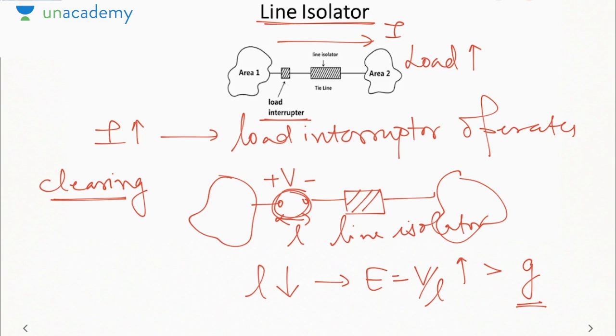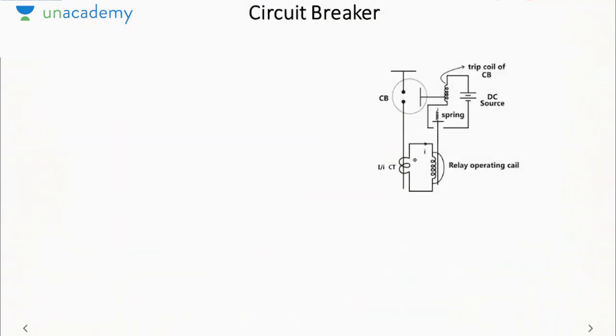So what it means is, there are 3 types of switches which operate under specific conditions. But I want to have a more general type of switch which can operate under any condition at my command. Because here I am not controlling any type of switch. One is operating under abnormal condition by itself, one is operating at full load condition by itself, other is operating at no load condition. But I want control. That is, I must be able to operate the switch whether abnormal conditions are there, or full load or no load. I must be able to control it. Such a switch is called your circuit breaker. So a circuit breaker is a switch which can operate under abnormal as well as normal conditions.